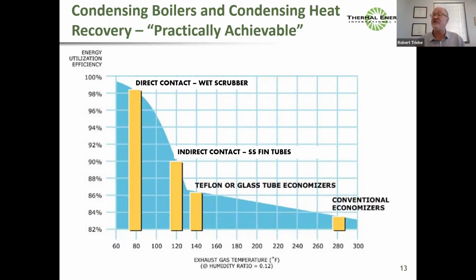That's 100% thermal efficiency. So this is a graph simply showing that conventional boiler feed water economizers, which would be made of carbon steel and frequently fail, typically can cool your flue gas down maybe another 100 degrees F or 200 degrees F, and your overall efficiency goes up 2 to 4% with a traditional feed water economizer. But the interesting thing is it's not a linear relationship. As we're cooling down the flue gas, it's linear until we hit the dew point. The moment that we hit the dew point, we begin to condense and the reaction is exponential. And so the more we can cool the flue gas down, the better, but it's not a linear relationship.